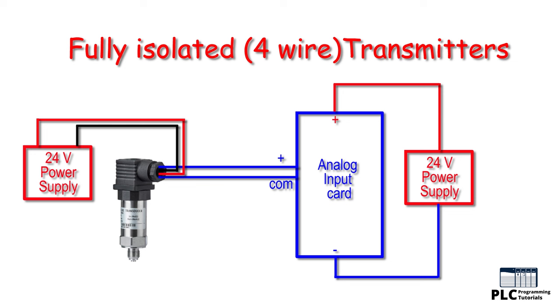Fully isolated 4-wire connection: the transmitter and control panel use separate power supplies, and the 4 to 20 milliamp signal flows through separate cable cores between the transmitter and the control panel. It is assumed that the power to drive the 4 to 20 milliamp loop is derived from the control panel. The advantage is that electrical interference on the voltage supply lines will not be transferred to the 4 to 20 milliamp signal line, reducing the risk of fault signals being received at the control panel end.